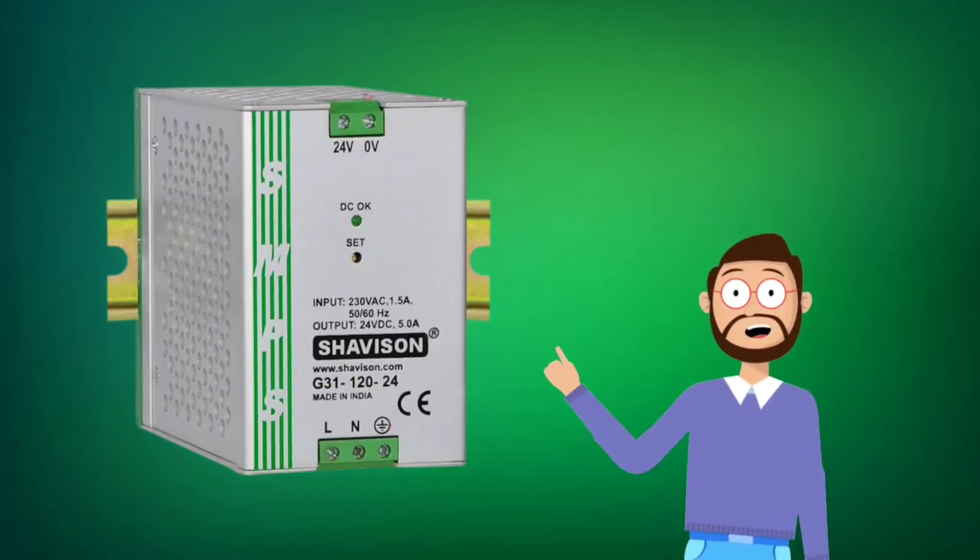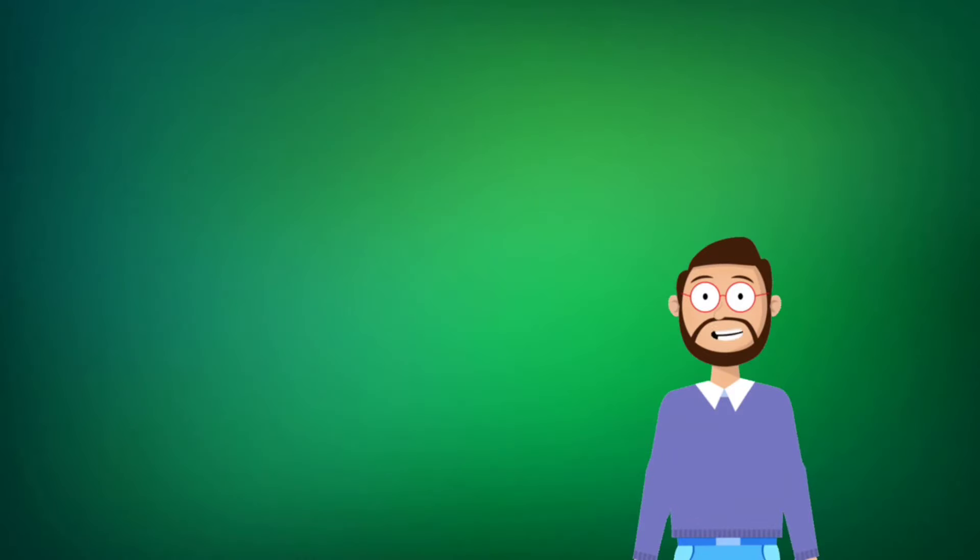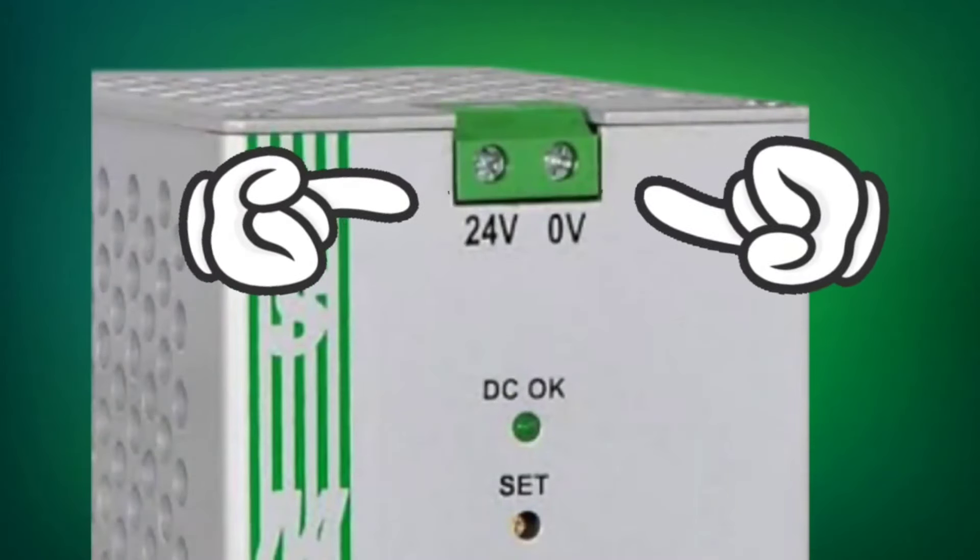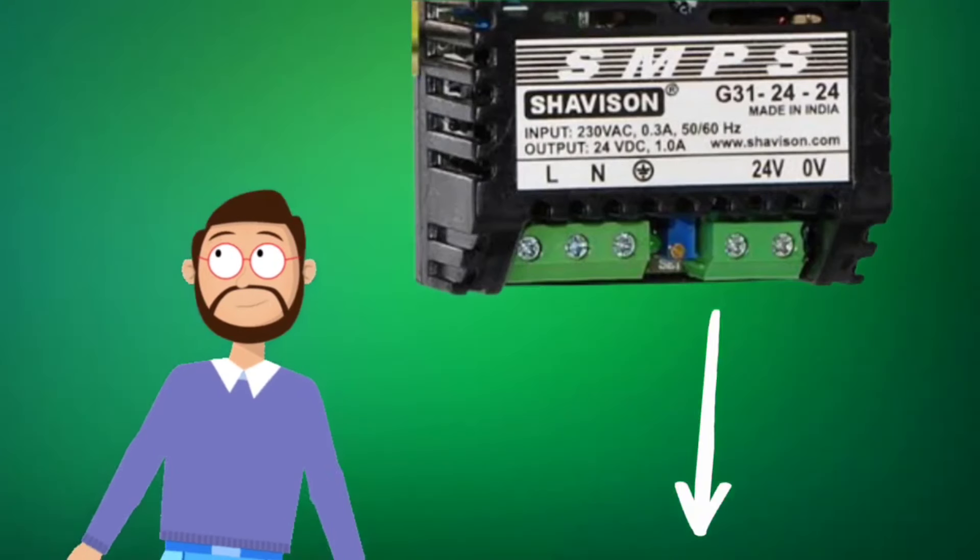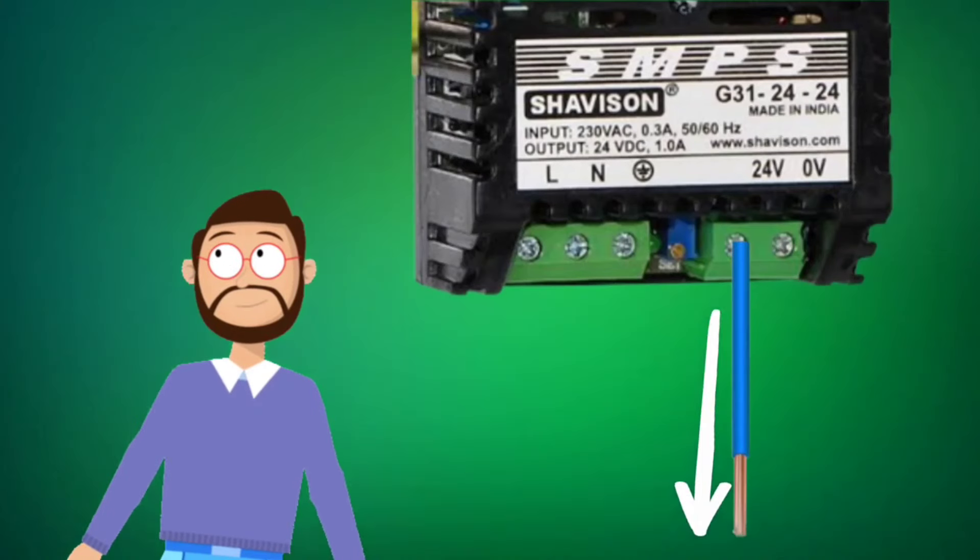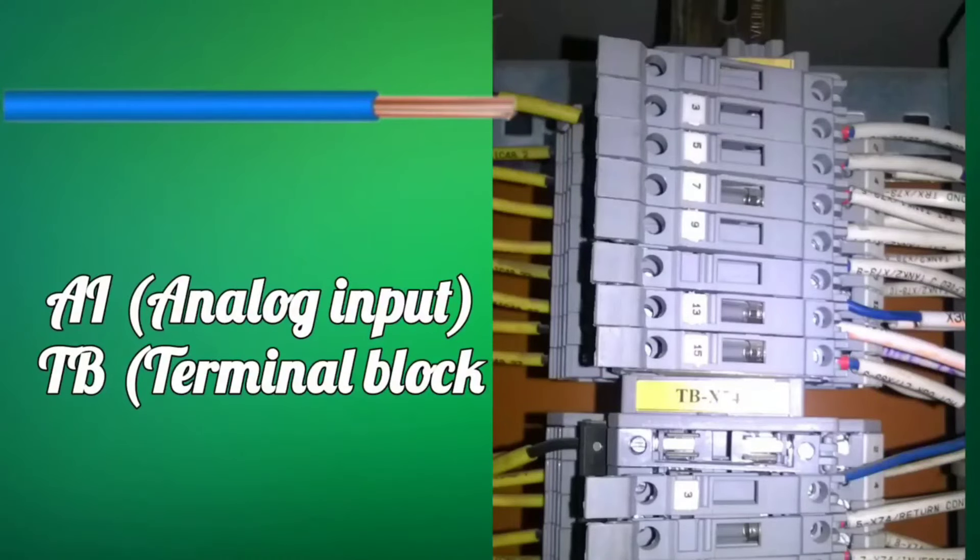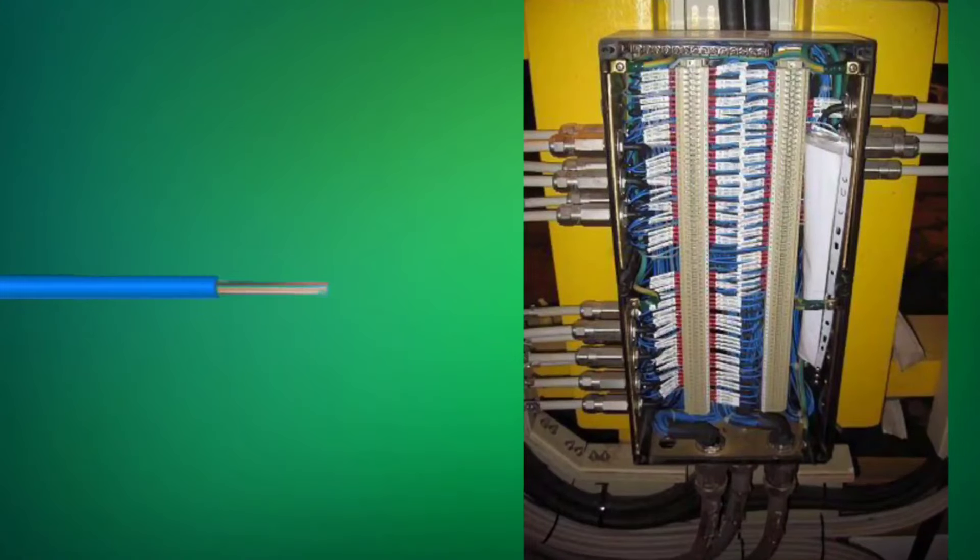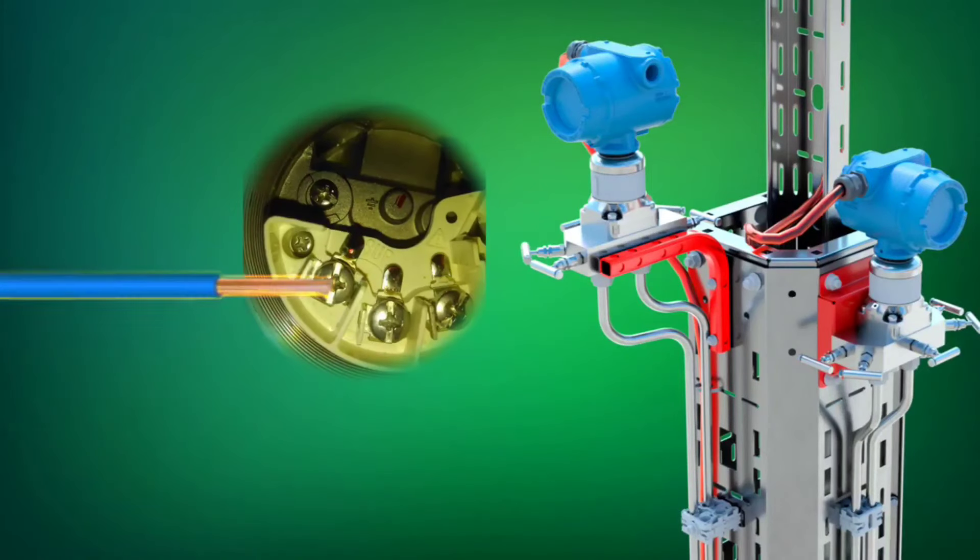There are two terminals at the output of SMPS. Usually, 24V is written on one of these and 0V is written on the other side. Now, whatever we are using SMPS or 24V DC supply, the one with 24V written on it, we send it to the PLC panel. In the PLC panel, this wire is connected to AITB. After this, the wire is passed through field JB to the transmitter and this wire is connected to the positive terminal of the transmitter.